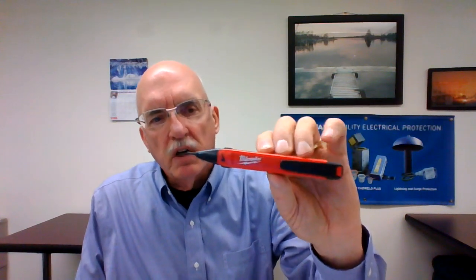So you go over to the receptacle here, you test it there, you get a signal, then you go above the ceiling, test it on that piece of equipment, you get no signal, then you come back to the original receptacle, test it again to make sure it's still working. And that way, you've tested not only the circuit you're working on up in the ceiling, but you've also proven that your proximity tester works. And it's all in the directions. When you buy that proximity tester, it's all in the directions on how to use them.